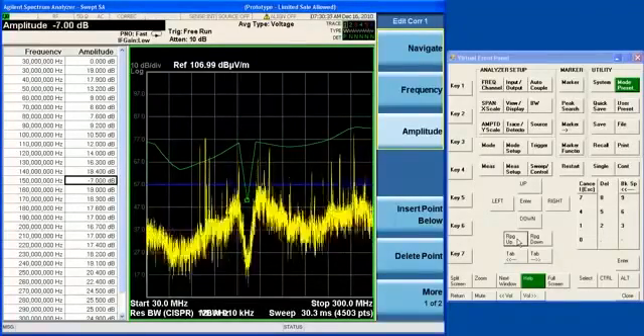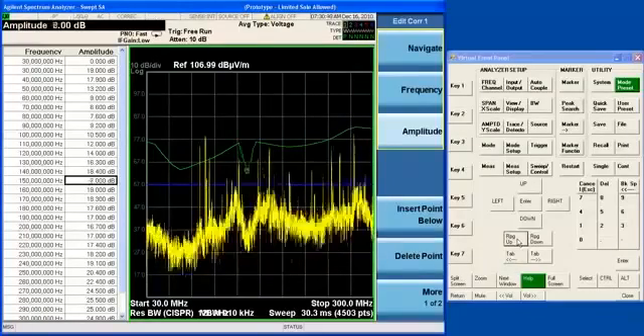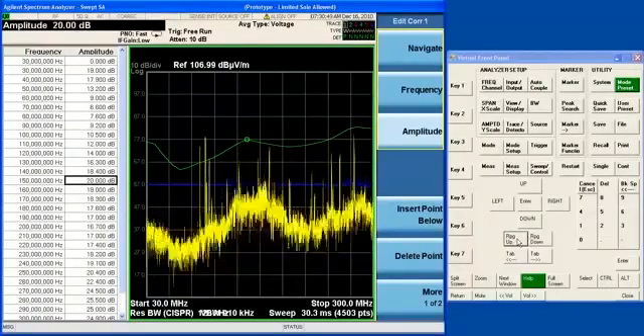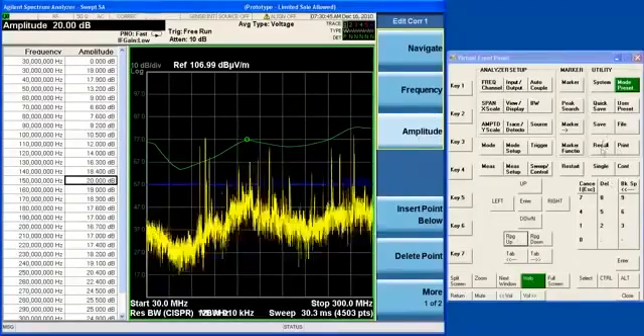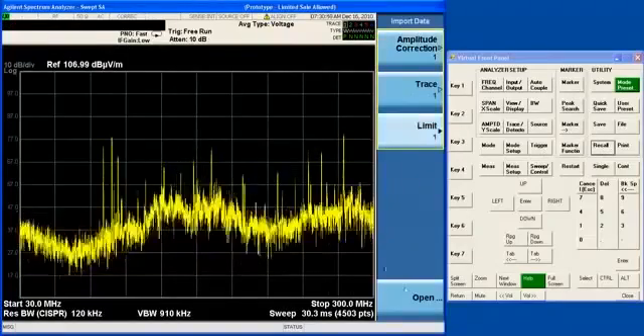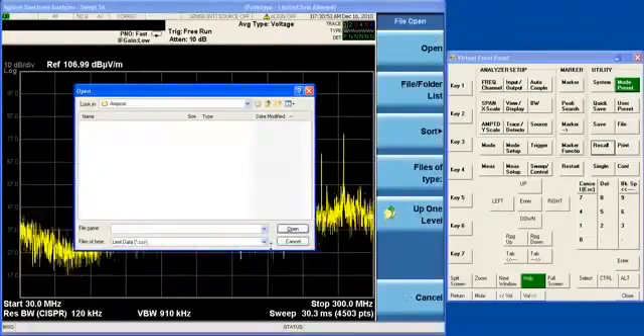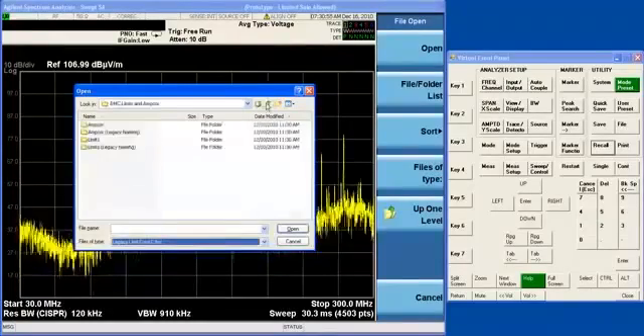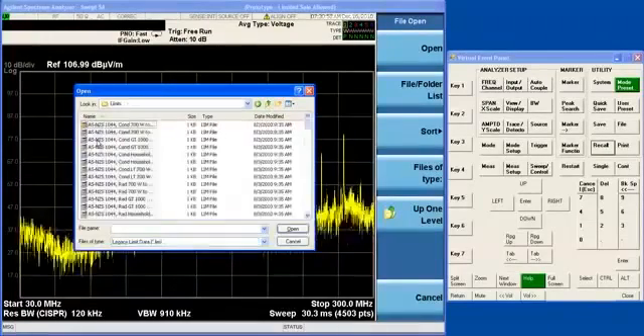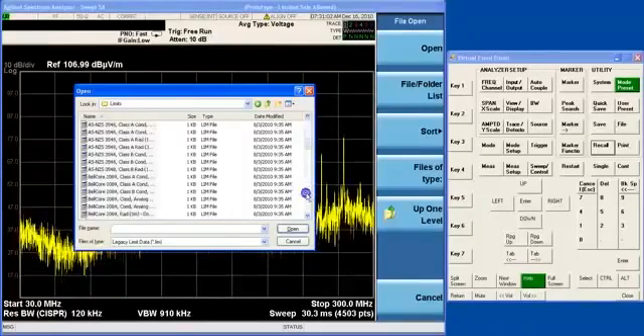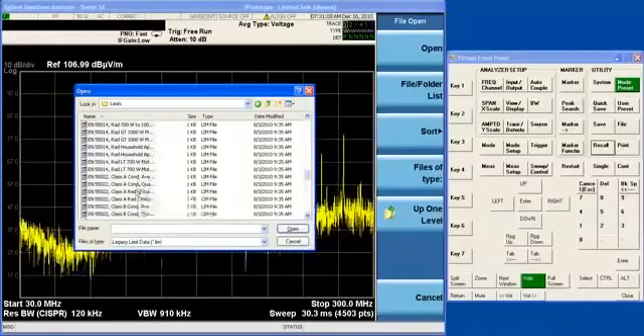Besides corrections, the analyzer also includes a set of limit lines, which are useful when you are making EMI measurements. If I go to the limit file type, again, the analyzer includes a set of preloaded limits, or you can define your own. In this case, I am going to choose an EN55022 limit for a 10 meter radiated.